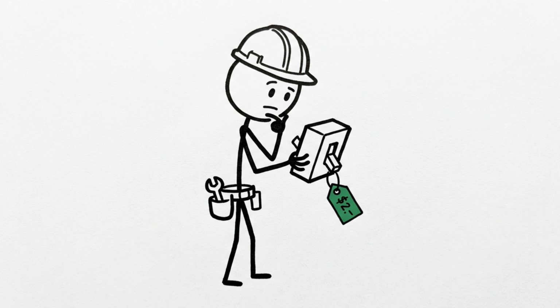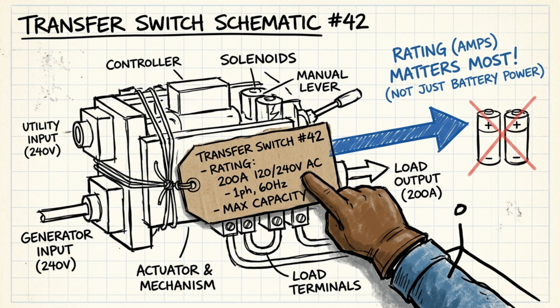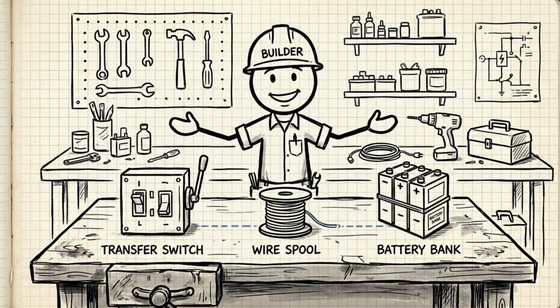The cheapest critical component in this entire build, a transfer switch or interlock kit, is the only reason any of this is legal or survivable. That switch has a rating on it that matters more than the size of your battery bank. Get that one number wrong, and it doesn't matter how many kilowatt hours you bought. By the end of this video, you'll understand exactly what a transfer switch actually does, why bigger battery doesn't mean safer house, and how to size the switch, the wire, and the battery together as one system.